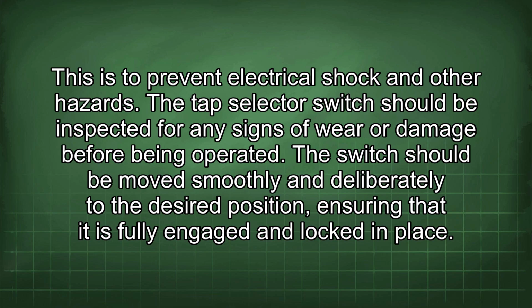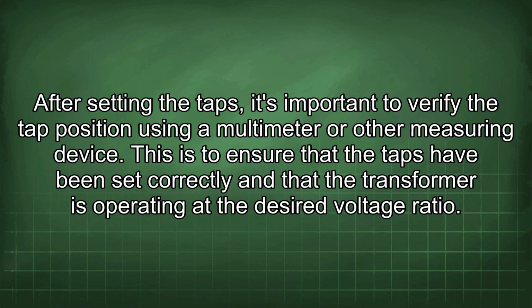The tap selector switch should be inspected for any signs of wear or damage before being operated. The switch should be moved smoothly and deliberately to the desired position, ensuring that it is fully engaged and locked in place. After setting the taps, it's important to verify the tap position using a multimeter or other measuring device. This is to ensure that the taps have been set correctly and that the transformer is operating at the desired voltage ratio.